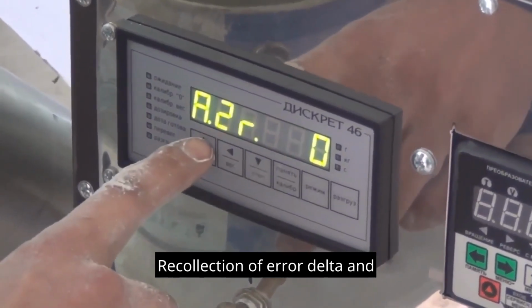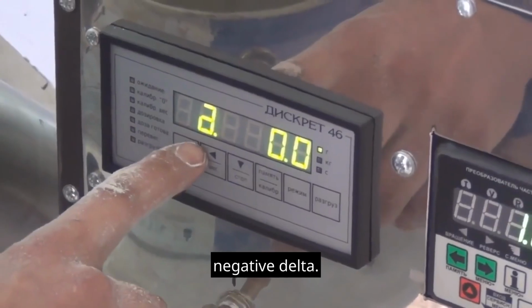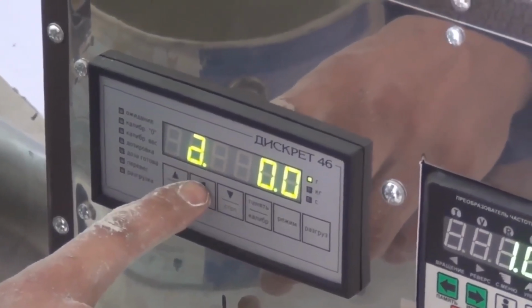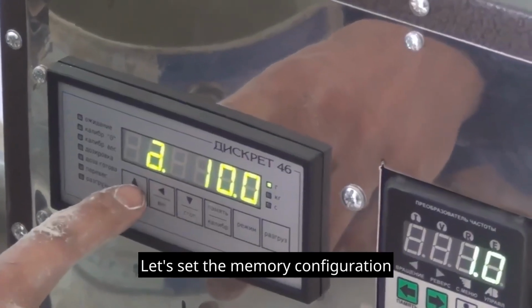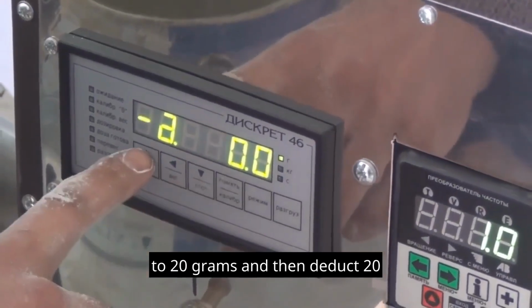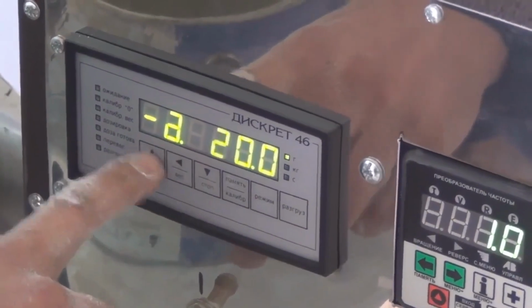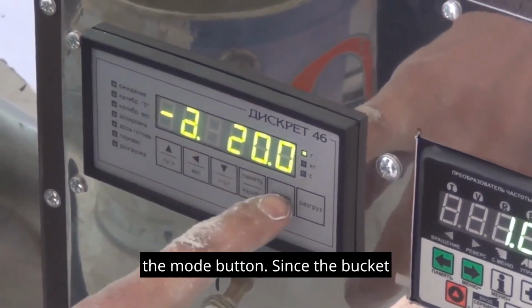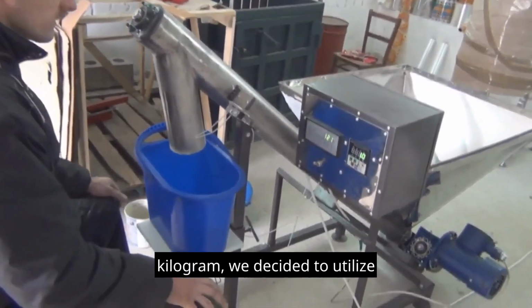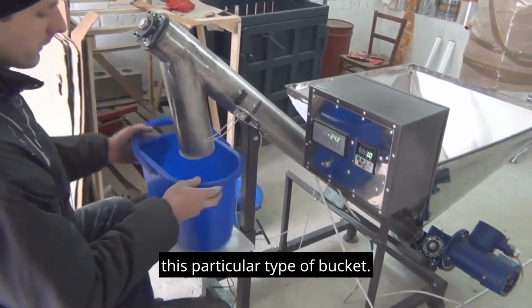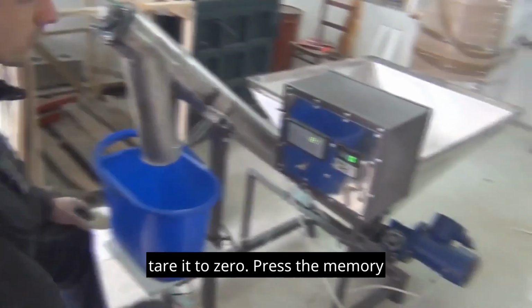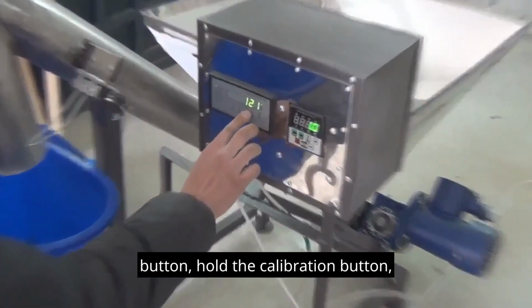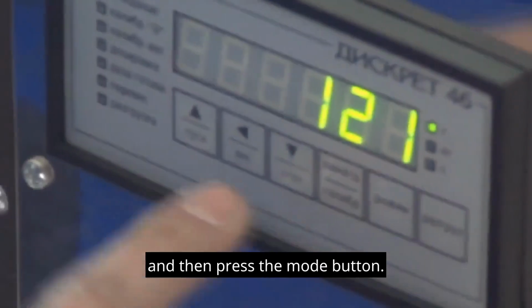Memory of error delta and negative delta. Let's set the memory configuration to 20 grams and then deduct 20 grams. Afterward, we exit and press the mode button. Since the bucket dose was not appropriate for 1 kilogram, we decided to use this particular type of bucket. We position it on the scale platform, tare it to 0. Press the memory button, hold the calibration button, and then press the mode button.